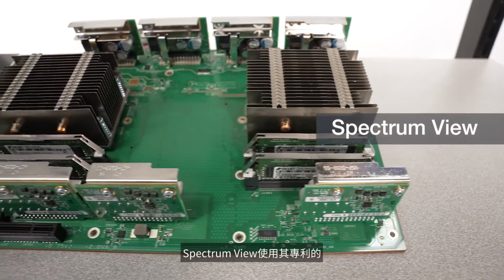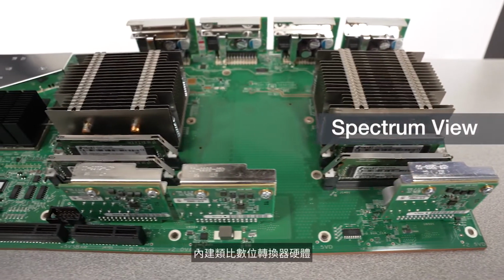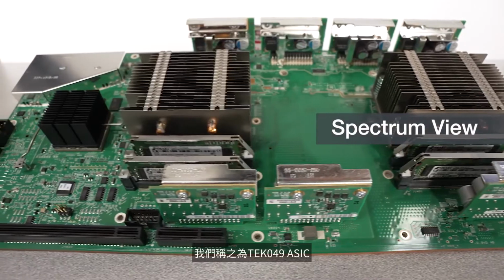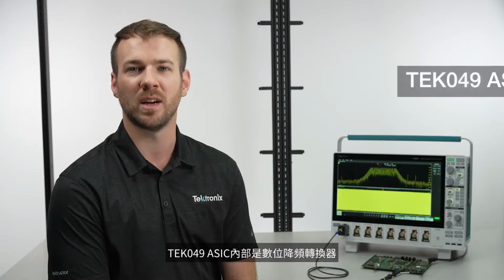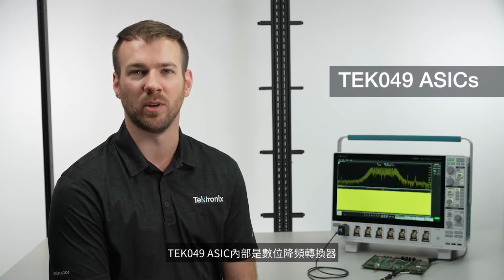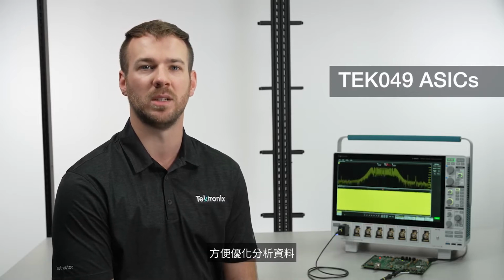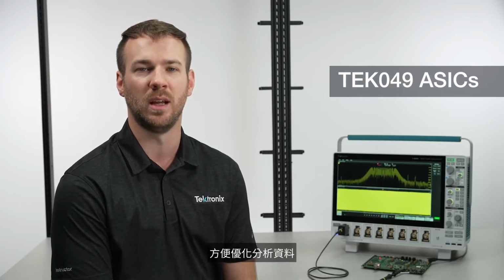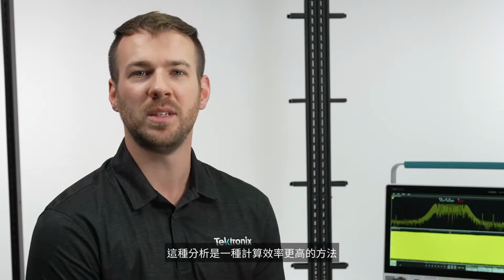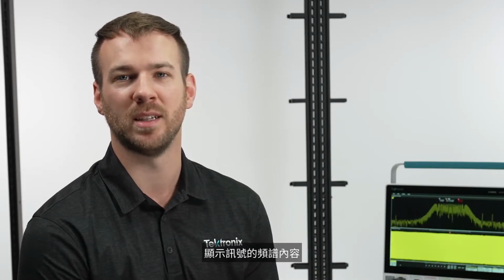SpectrumView uses patented hardware built into the analog-to-digital converter, which we call the TEK049 ASIC. Inside the TEK049 ASICs are digital down converters, which optimize analysis based on the selected center frequency and span settings. This analysis is a more computationally efficient way to display the spectral content of the signal, enabling best-in-class analysis and measurement results.